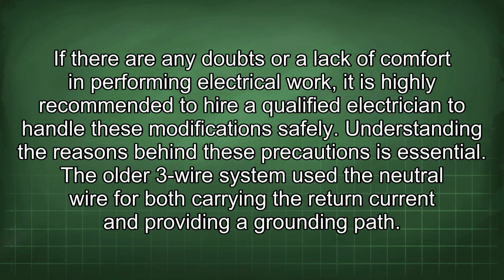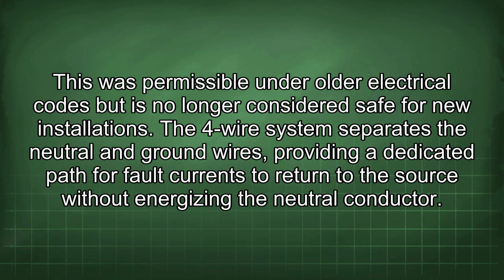Understanding the reasons behind these precautions is essential. The older 3-wire system used the neutral wire for both carrying the return current and providing a grounding path. This was permissible under older electrical codes but is no longer considered safe for new installations. The 4-wire system separates the neutral and ground wires, providing a dedicated path for fault currents to return to the source without energizing the neutral conductor.